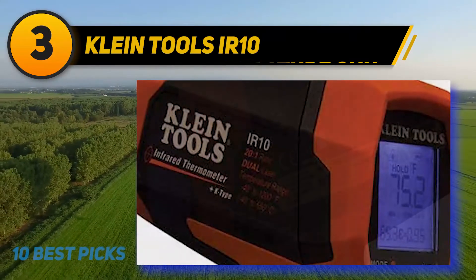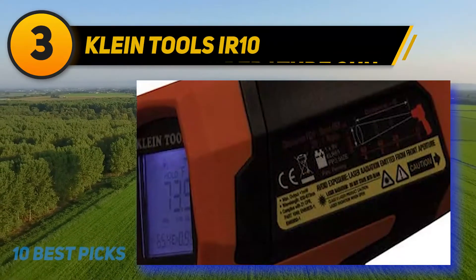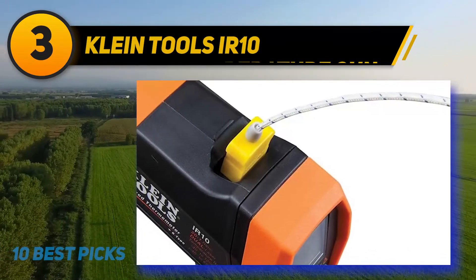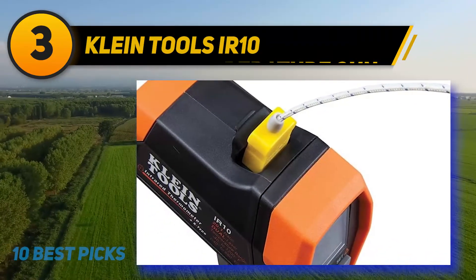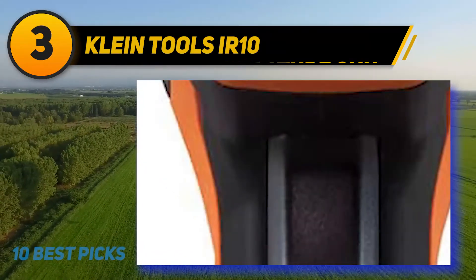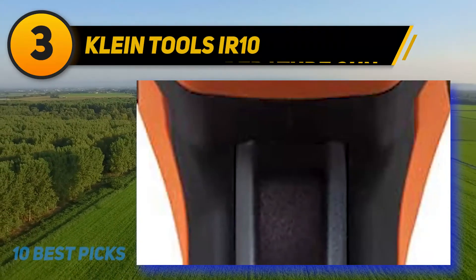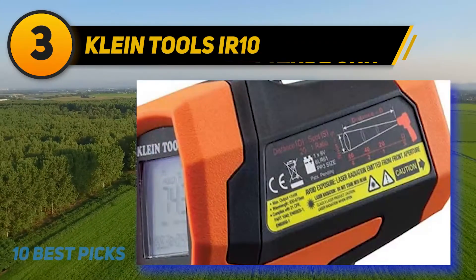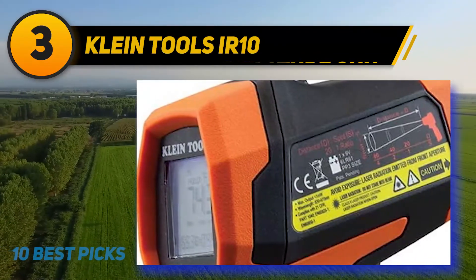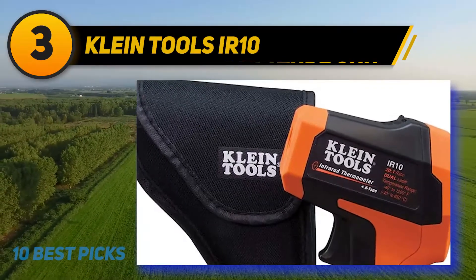There are dual targeting lasers that give you a more accurate measurement of the area you're aiming at, plus it has a distance-to-spot ratio of 20-1, so you don't need to be right up against the object you're testing. Both the IR and the K-type probe have the same measurement range of minus 40 to 1,200 degrees Fahrenheit. The digital display includes backlighting, so you'll be able to see the screen in low light. The emissivity is adjustable from 0.1 to 1.0, which helps when targeting different types of surfaces.